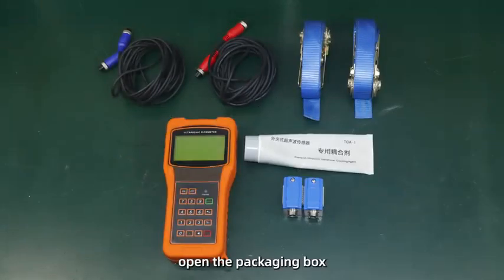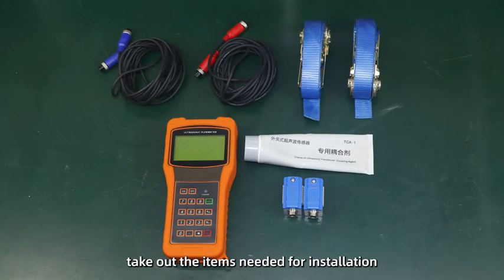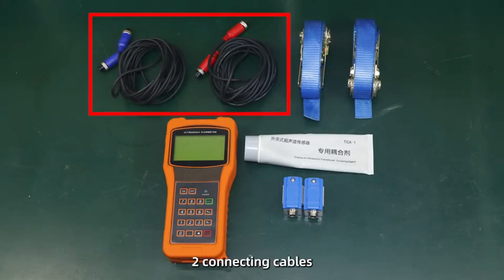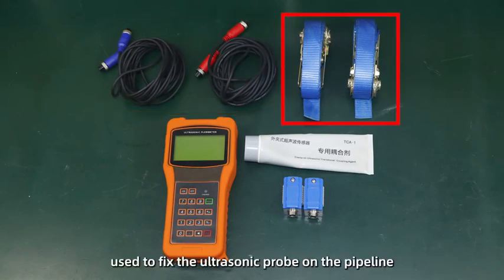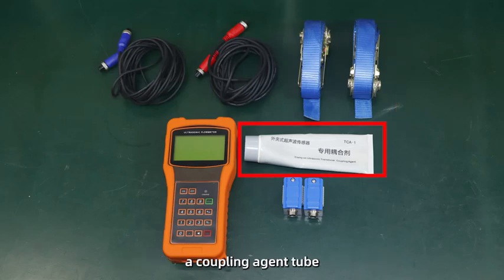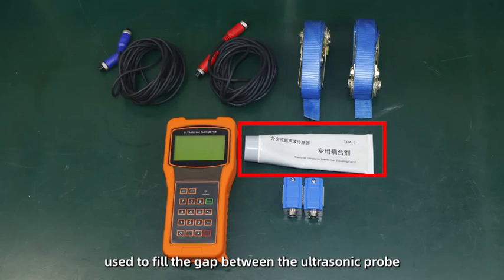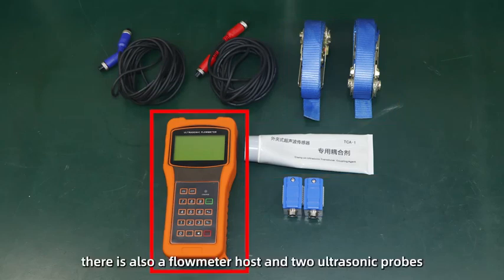Open the packaging box. Take out the items needed for installation. 2 connecting cables, for connecting the Flowmeter host and the ultrasonic probe. 2 tensioners, used to fix the ultrasonic probe on the pipeline. A coupling agent tube, used to fill the gap between the ultrasonic probe and the pipeline, making the measurement more accurate. There is also a Flowmeter host and 2 ultrasonic probes.